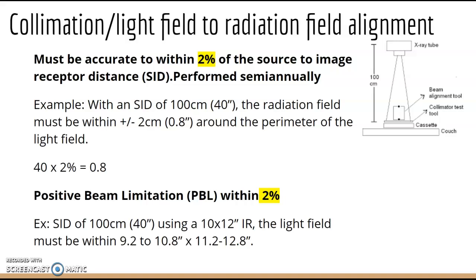Collimation — light field alignment — tests how accurate your light field is compared to what's actually produced on your image. In the clinical world, what your light field is open to should match your exposure. It must be accurate within 2% of the SID. If given a word problem with SID in centimeters or inches, you'll need to calculate that 2%.